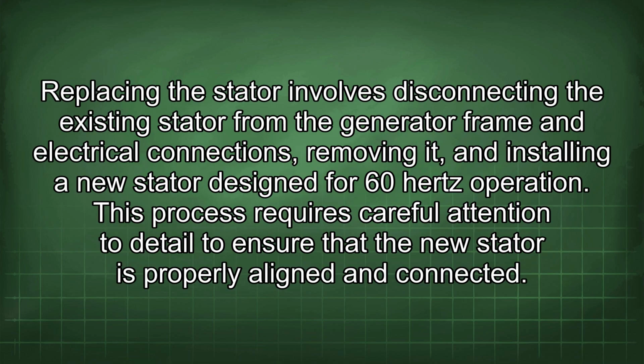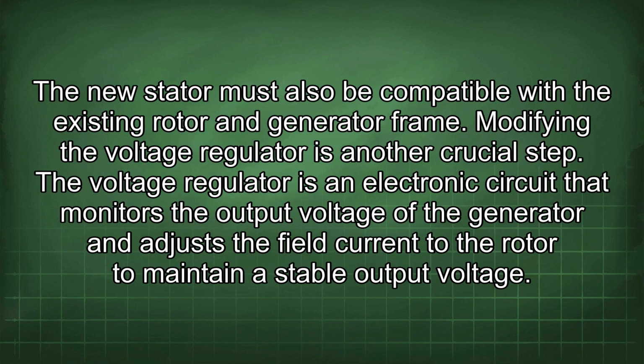Replacing the stator involves disconnecting the existing stator from the generator frame and electrical connections, removing it, and installing a new stator designed for 60 Hz operation. This process requires careful attention to detail to ensure that the new stator is properly aligned and connected. The new stator must also be compatible with the existing rotor and generator frame. Modifying the voltage regulator is another crucial step. The voltage regulator is an electronic circuit that monitors the output voltage of the generator and adjusts the field current to the rotor to maintain a stable output voltage.